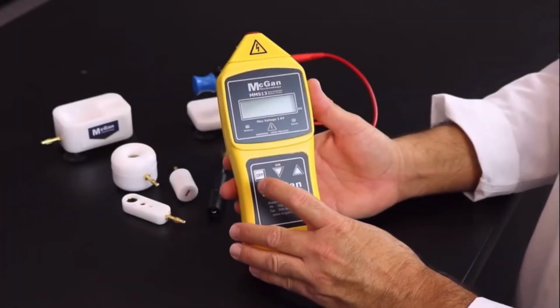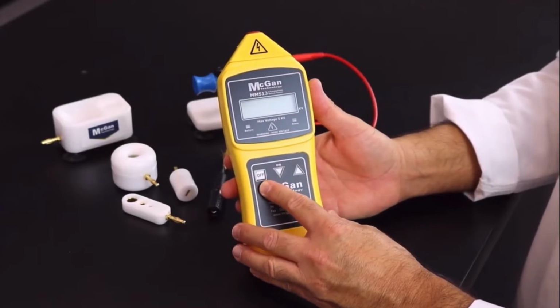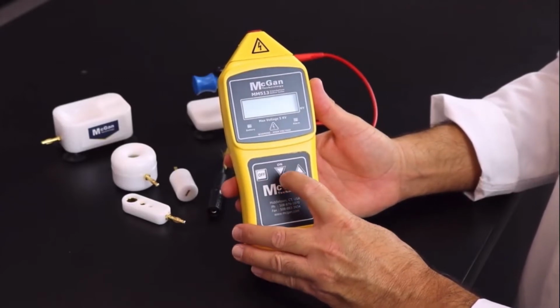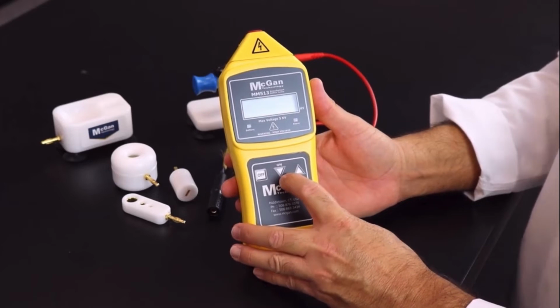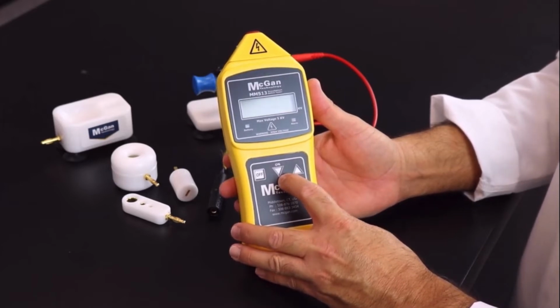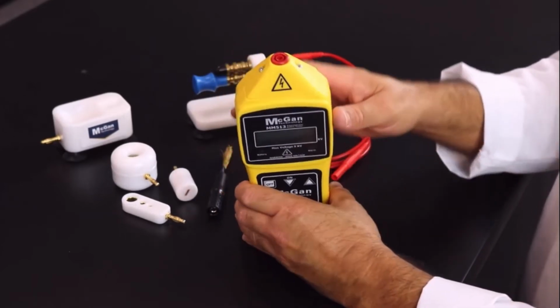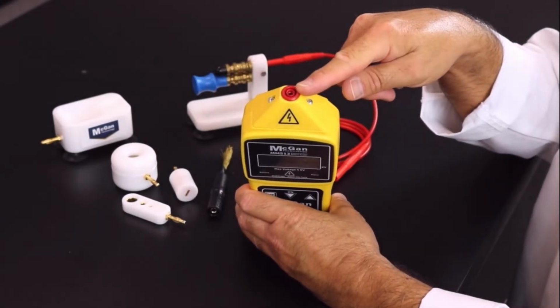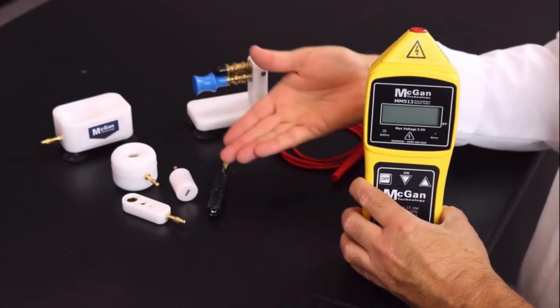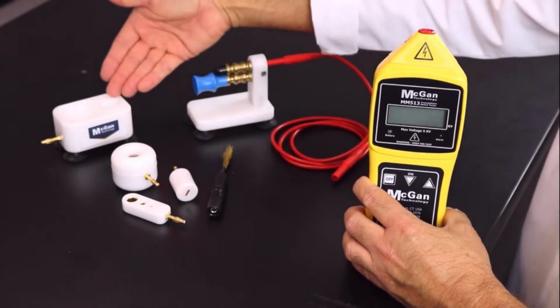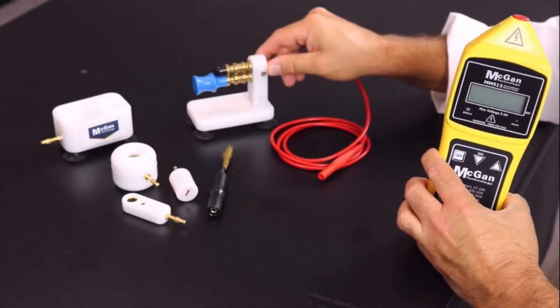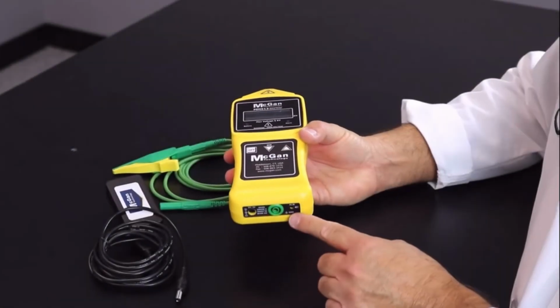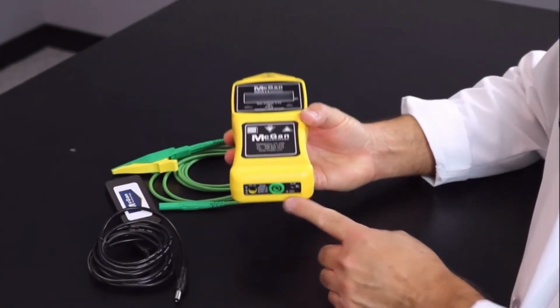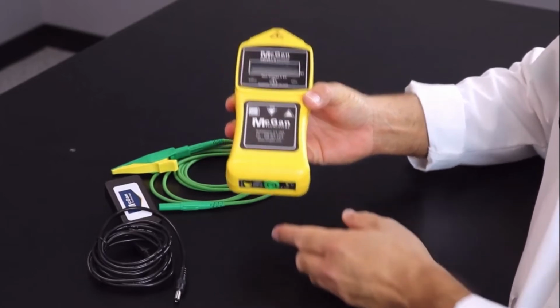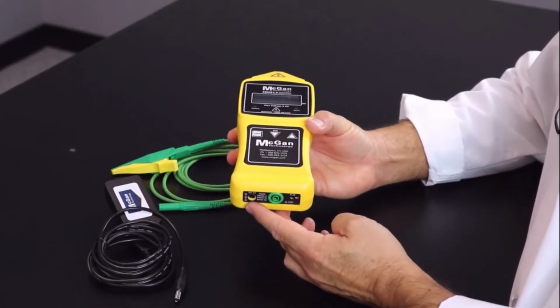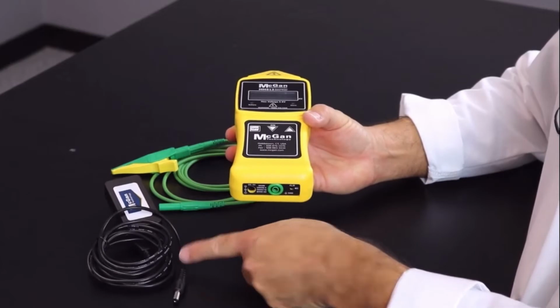On the front bottom of the unit, you're going to see an off button, an on button, and then the up and down arrows to adjust the desired voltage dependent on the accessory being used. On the top of the unit is a red base unit port. This connects to the accessories, the saddle block, and then the red wire for the wire testing accessory. On the bottom is the green grounding port for the use of the green grounding wire and alligator clip. On the bottom as well, you'll see the power supply to connect the adapter to charge the unit.